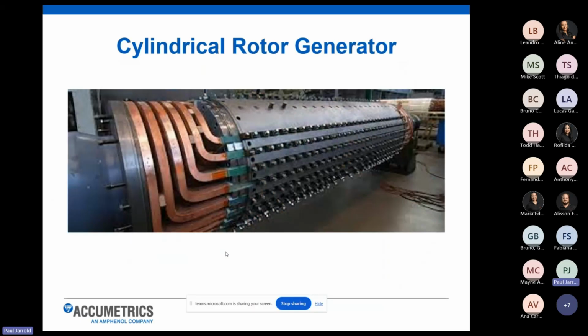So this is a picture of what a cylindrical generator rotor looks like. In that first slide that I showed for the ground fault, that fault occurred on the end of the rotor between the field windings here, an area where they usually put what they call a retaining ring or retaining cap on each end of the cylindrical rotor. And that's where that one customer had a fault happen. However, a fault can also occur somewhere along the path of the rotor itself. Anywhere in any of these slots that are cut into the cylindrical rotor, a fault can happen.